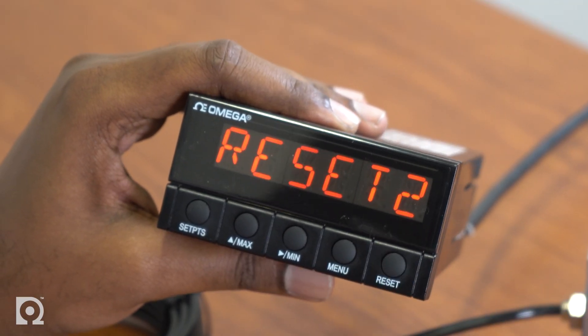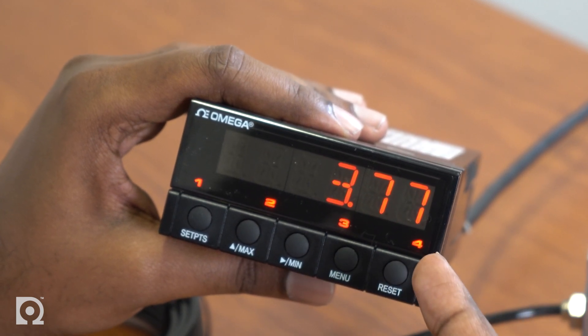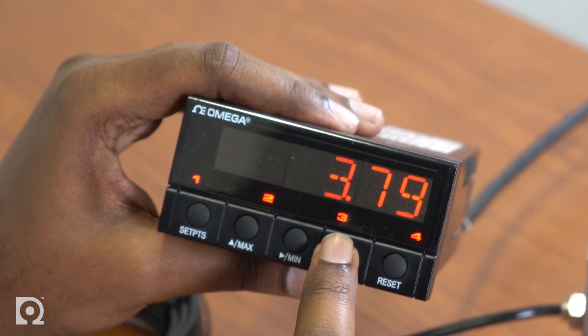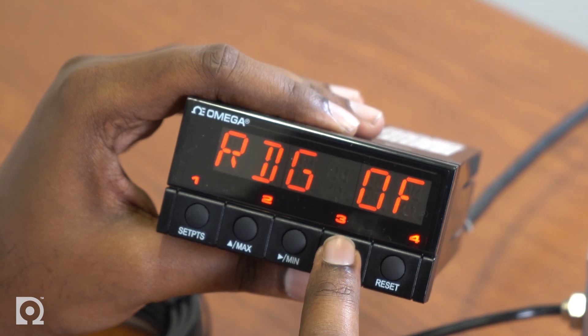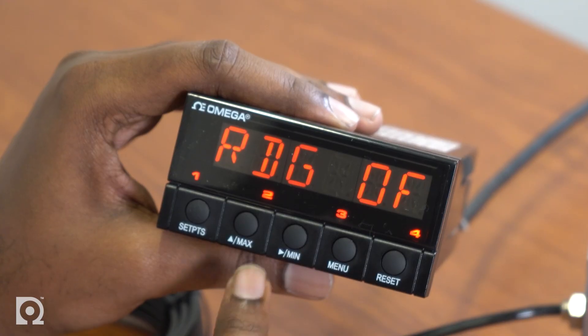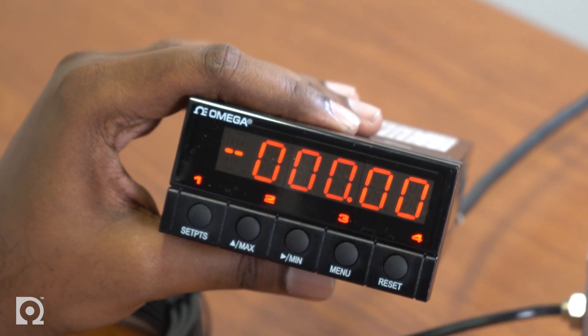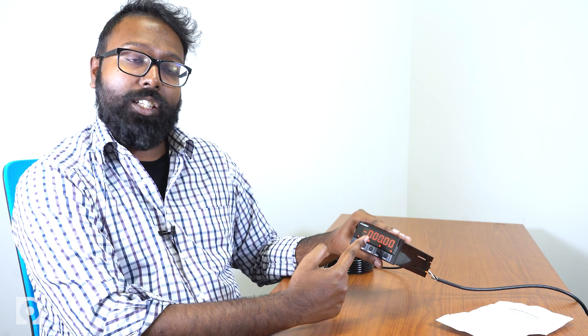Now you'll notice that there is a small offset in the meter, because most load cells have an inherent zero offset. To offset this value at no load, press the menu button continuously until you see RDG OF. RDG OF stands for reading offset. Press the min button to go into this menu, and it'll show you negative zero zero zero point zero zero. Now put a value over here to offset the value that we saw initially. At no load, we saw three point eight.